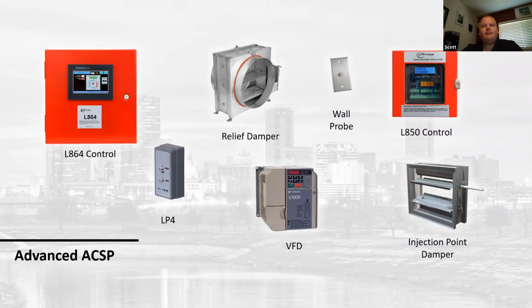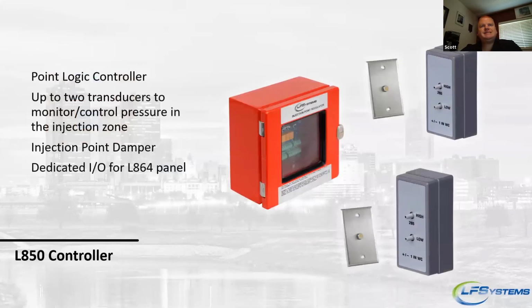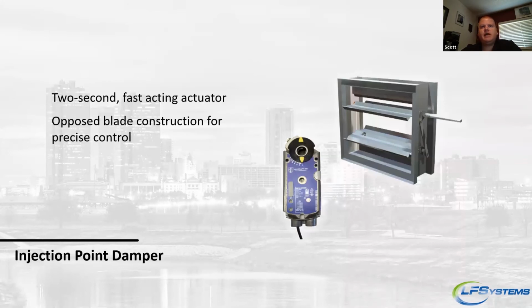The 850 controller is an independent point logic controller. It controls up to 2 pressure transducers and an injection point damper. It also has a dedicated I/O for the 864 panel. The injection point damper uses a 2-second fast-acting actuator. This is the fastest actuator in the industry. We actually worked with the manufacturer to develop this for our needs. And then we use an opposed blade damper for precise air control. So let's take a look at how this lays out.